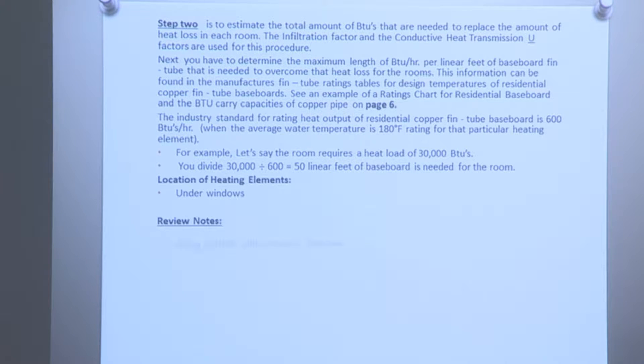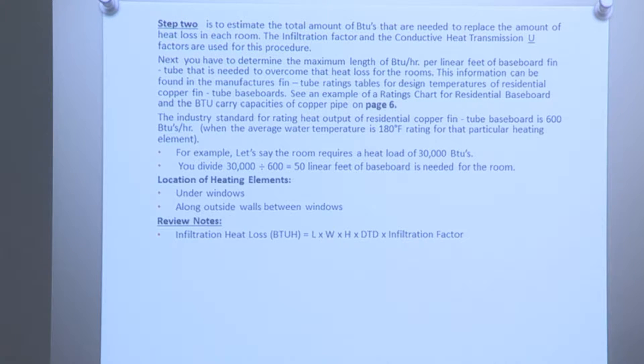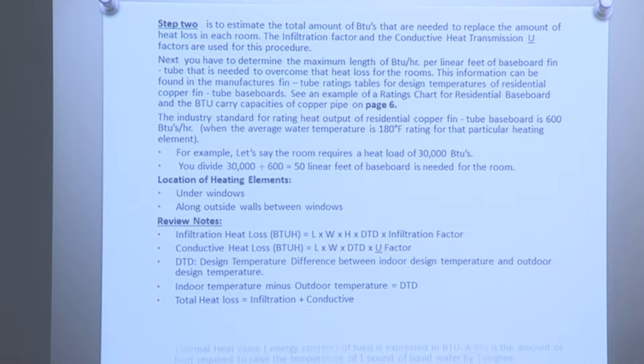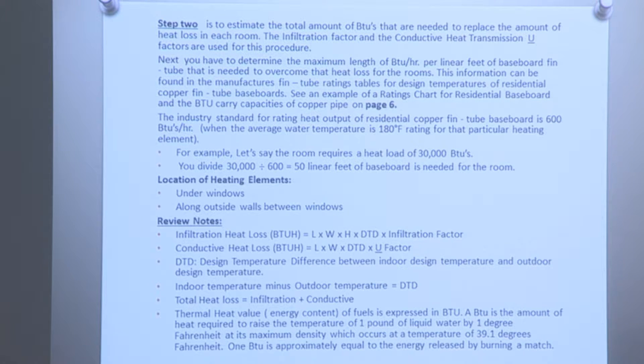Location of heating elements: under windows, along outside walls, between windows. Infiltration heat loss BTU equals L times W times H times DDT times the infiltration factor. Conductive heat loss BTU equals L times W times DDT times the U-factor. DTD is the design temperature difference between indoor and outdoor design temperatures. Total heat loss equals infiltration plus conductive. A BTU is the amount of heat required to raise the temperature of one pound of liquid water by one degree Fahrenheit at its maximum density, which occurs at 39.1 degrees Fahrenheit.